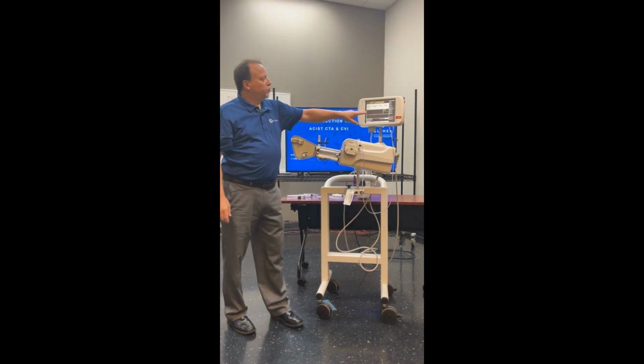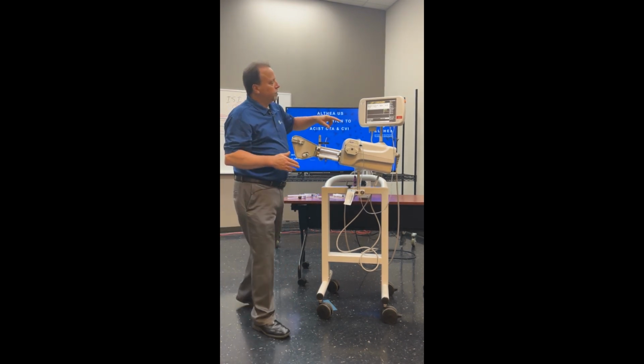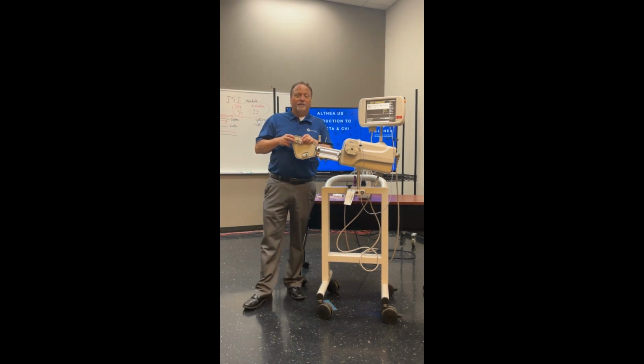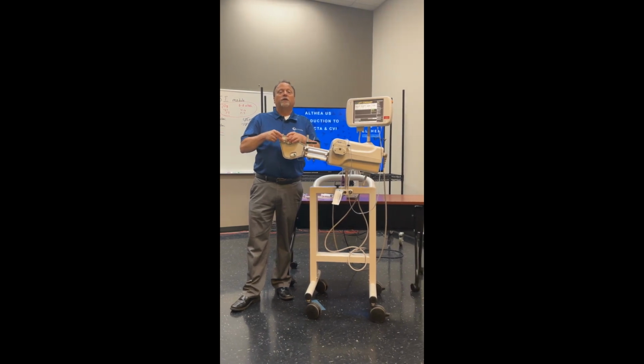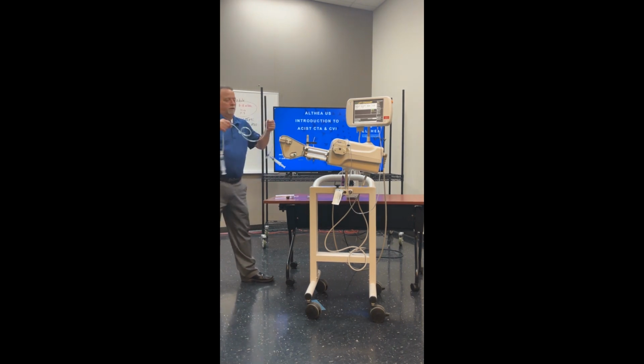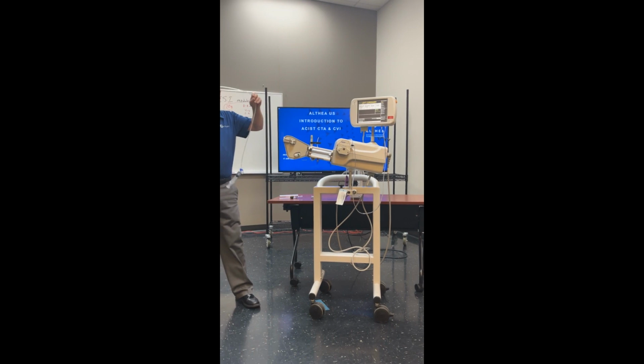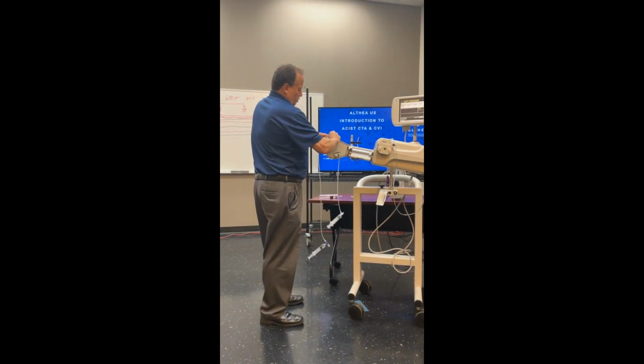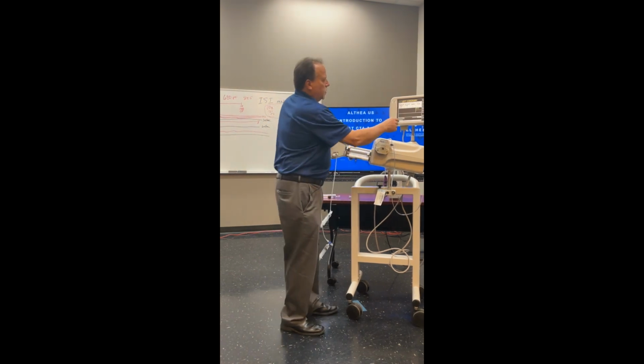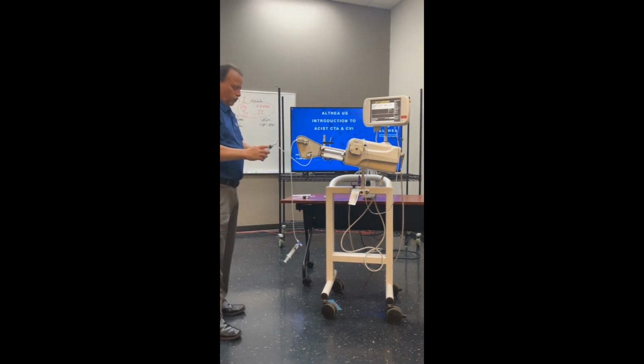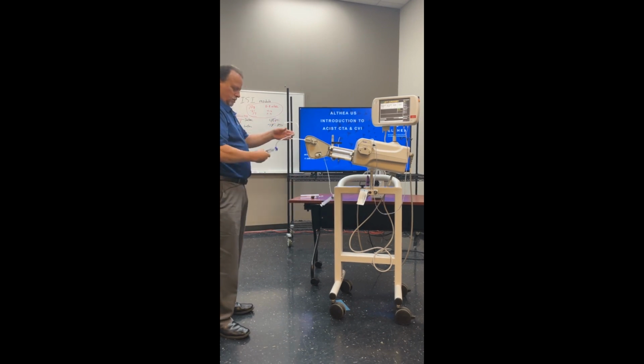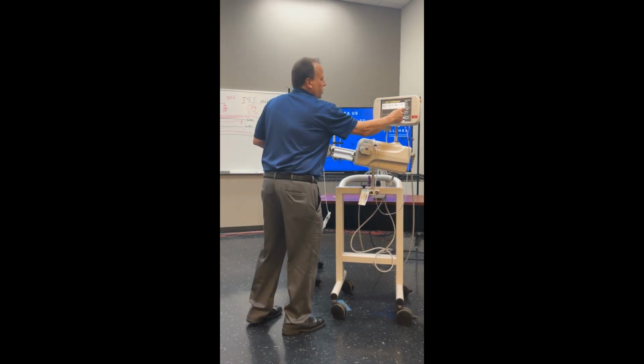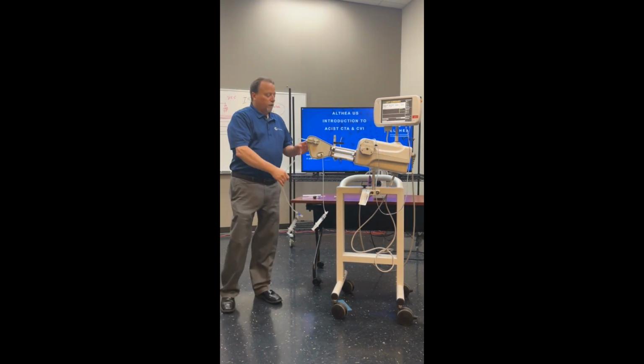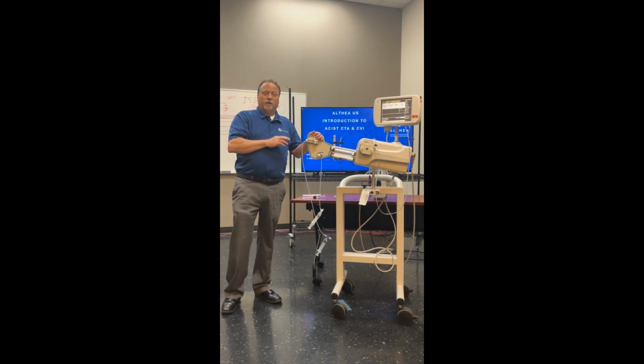So let's look at some of the indicators we have here that we haven't satisfied the sensors with. One is air detected. This is the ACD, air column detector sensor. It will detect any air in the tubing going to the patient. And you will use a jig, something like this. If you go to our training, this will be demonstrated further. And we will use water to purge this, to get rid of the air column detector, and that's gone now. So we will use an air bubble to go back and forth in the ACD to verify that the sensor is working.